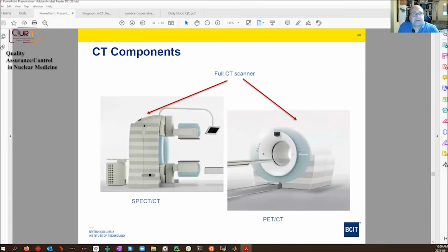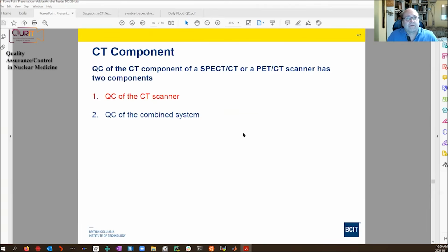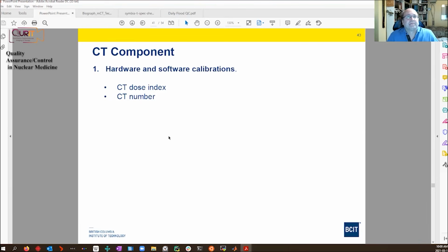Just very quickly, CT components. Modern SPECT-CT and PET-CT have either a full CT scanner or CT components, an X-ray tube and CT detectors hanging off them. Again, they have these aspects, and I'm not going to go over them in detail. We can break them into two parts, though: the QC of the scanner and the QC of the combined system. Calibrations are important for the scanner itself. I'm putting these in the category of calibrations, though they may not fit there, and that is measuring the CT number. That is the relative value of the attenuation coefficient in the object you've scanned.